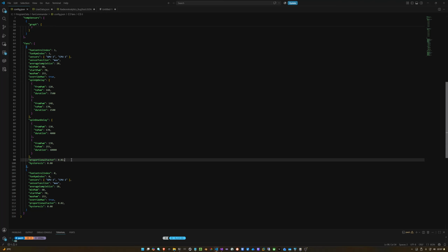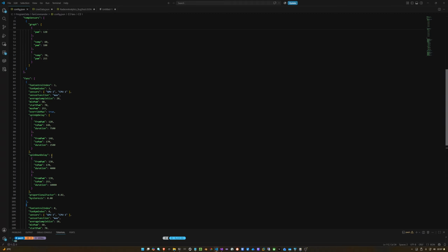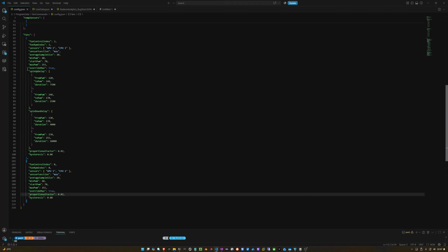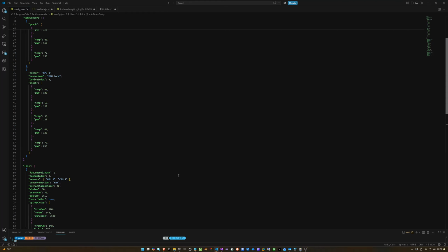If you take PID control, which is the best, you have minimal error. Here you have constant error present. It's not too large. I have it set still because I'm testing my software, and I wanna show you. Like you can see, I didn't put spin up delay for my back fan. I could basically put that here and configure it.